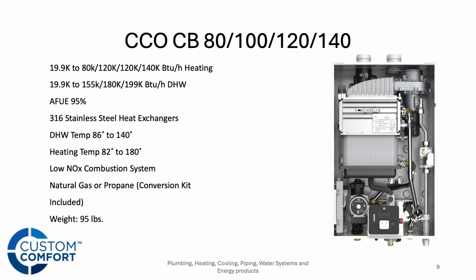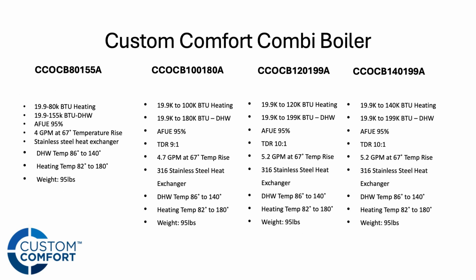So diving into a few more specs on the combi, and the 4 different sizes we have for the custom comfort combi boiler. We like to keep it simple when it comes to custom comfort, even down to the part numbers. So our part numbers are going to tell you a lot about the boiler itself in terms of the heating input, as well as the domestic input. And so when you look at our first boiler, the CCO CB 80-155, that's going to be 80,000 BTUs of heating input, as well as 155,000 BTUs of domestic input. And that 155,000 BTUs domestic input is going to give you 4 gallons a minute on the domestic side.